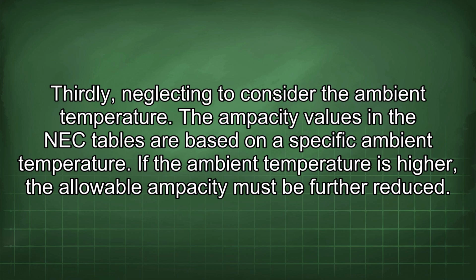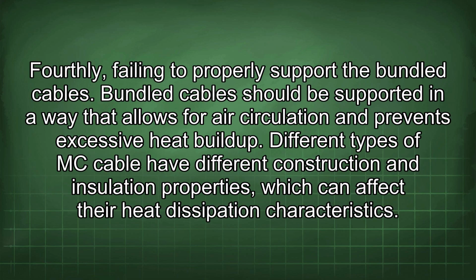Thirdly, neglecting to consider the ambient temperature. The ampacity values in the NEC tables are based on a specific ambient temperature. If the ambient temperature is higher, the allowable ampacity must be further reduced. Fourthly, failing to properly support the bundled cables. Bundled cables should be supported in a way that allows for air circulation and prevents excessive heat buildup.